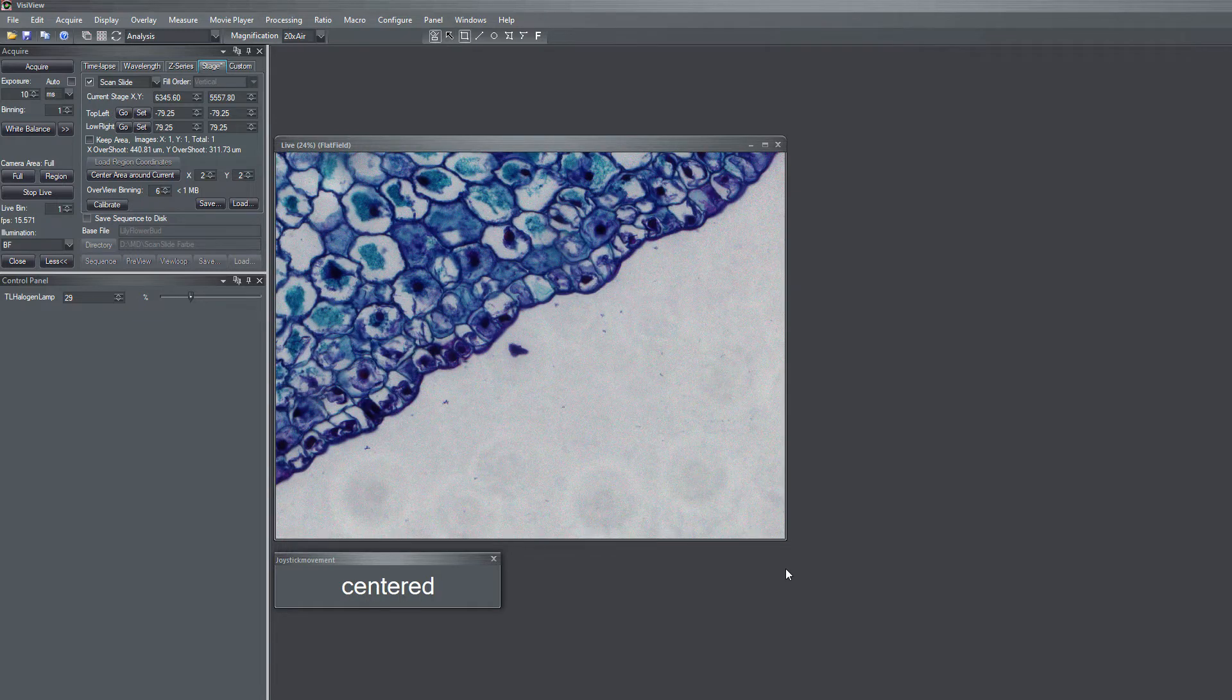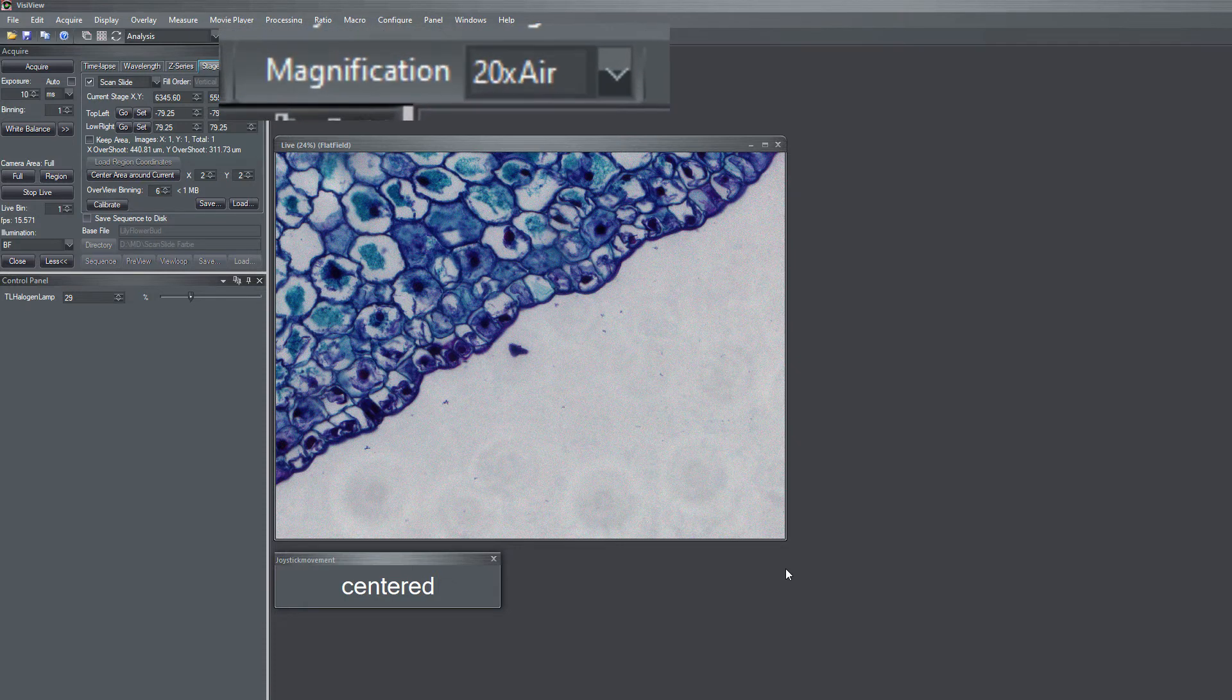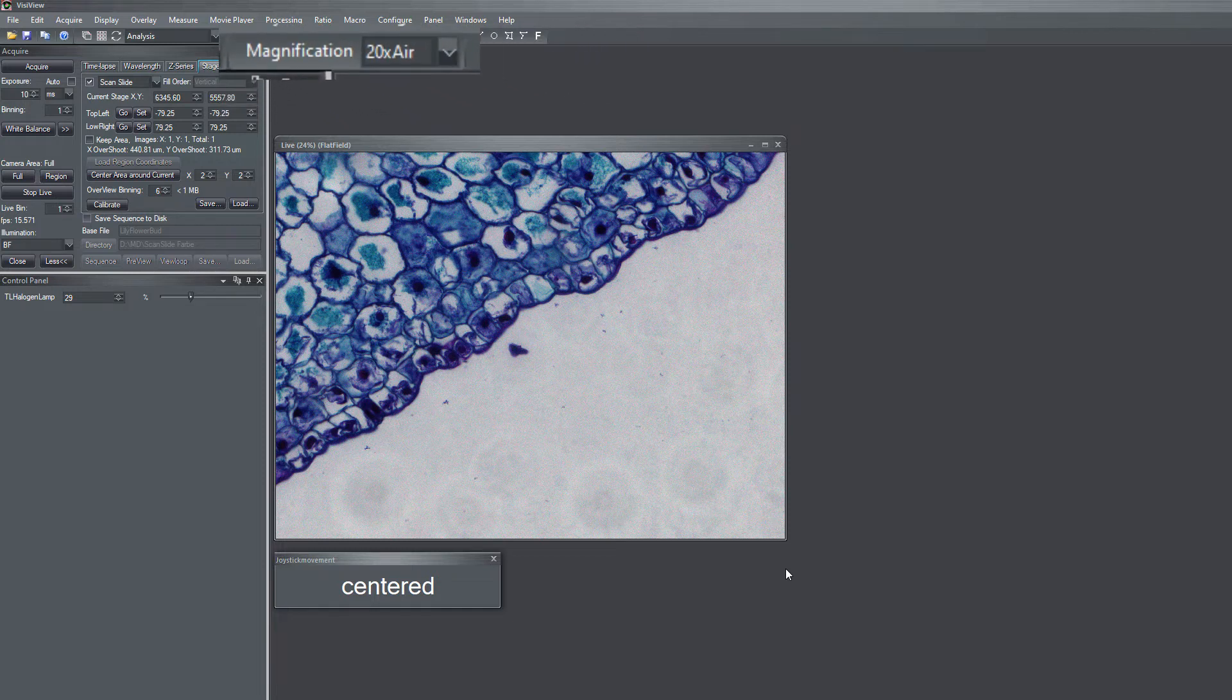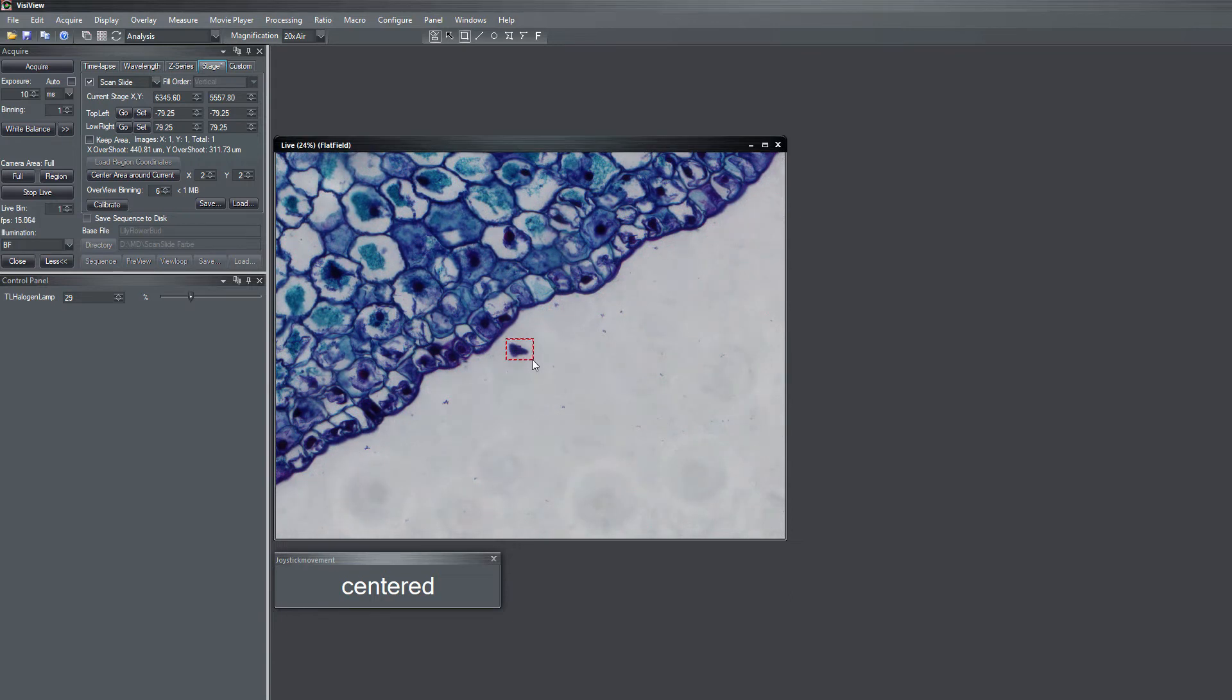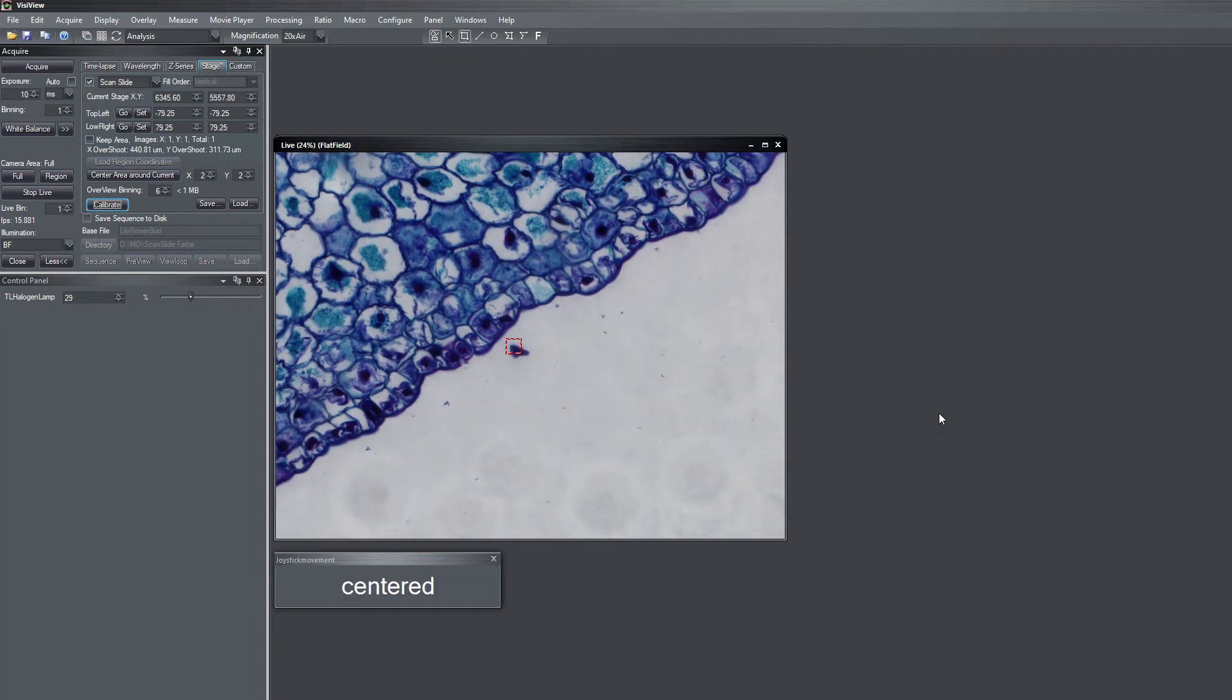Now we are ready for the next step: scan slide calibration. Before we start with the calibration, be sure that your sample is properly fixed in the stage and that your system uses a proper magnification. Then you start a live image and draw a rectangular region around a significant object in the middle. The region should be smaller than 100 by 100 pixels.